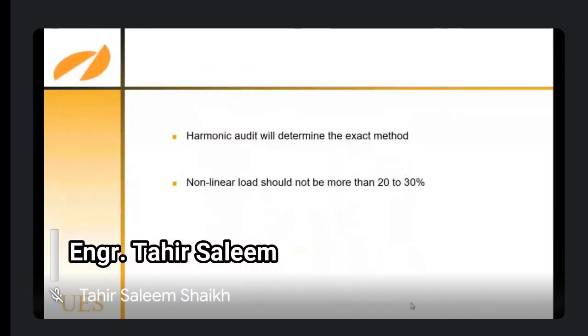This is a combination, and this is more expensive. So you have to decide yourself what the solution is. A harmonic audit will determine the exact method. If you are using a normal transformer, the non-linear load should not be more than 20 to 30% of the total load. These are the simple limitations.